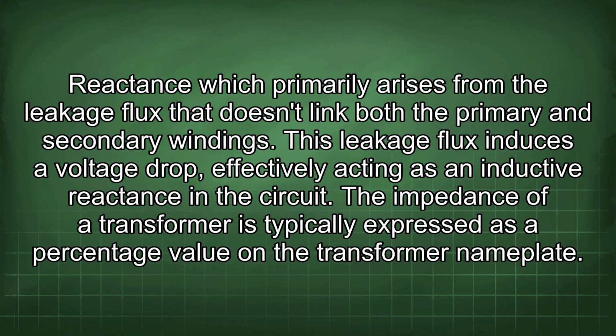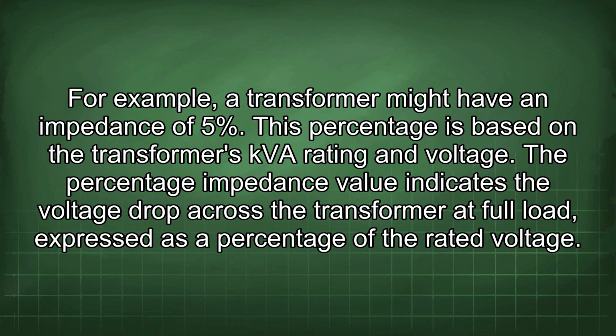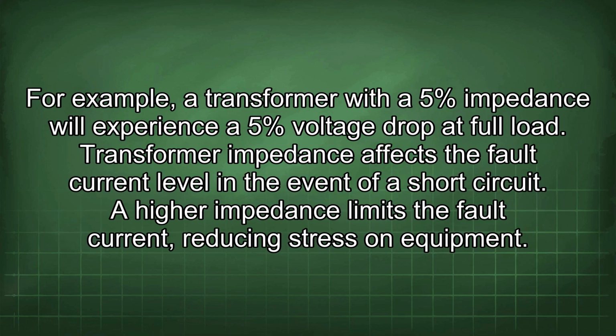The impedance of a transformer is typically expressed as a percentage value on the transformer nameplate. For example, a transformer might have an impedance of 5%. This percentage is based on the transformer's kVA rating and voltage. The percentage impedance value indicates the voltage drop across the transformer at full load, expressed as a percentage of the rated voltage. For example, a transformer with a 5% impedance will experience a 5% voltage drop at full load.